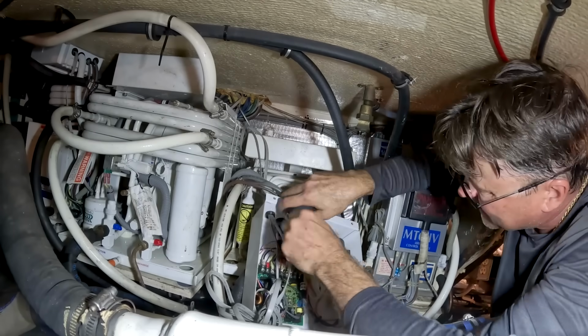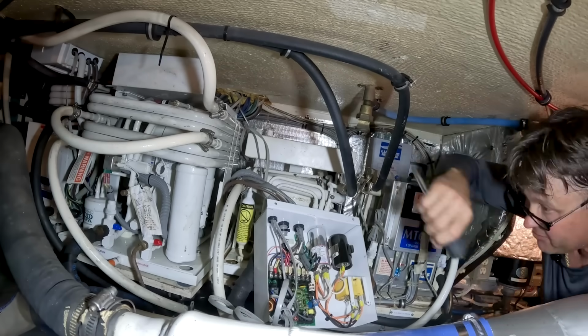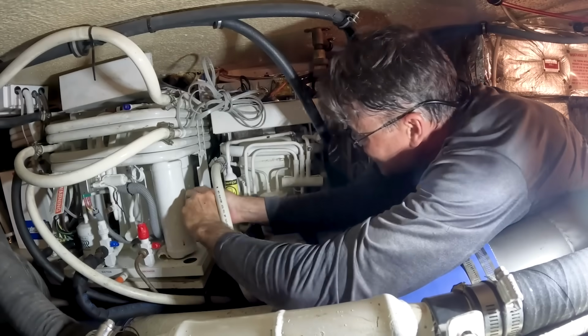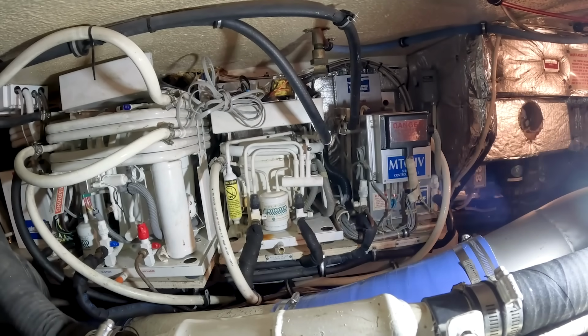I'm going to disconnect the compressor. See if I can get the fan to run. I'm wondering if we're starting to think our compressor is shorted to ground. So I'm going to ohm out one more thing here. All right, first we'll make sure the breaker's off one more time. And the breaker is off.